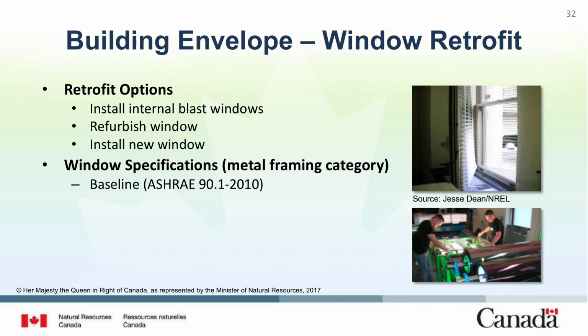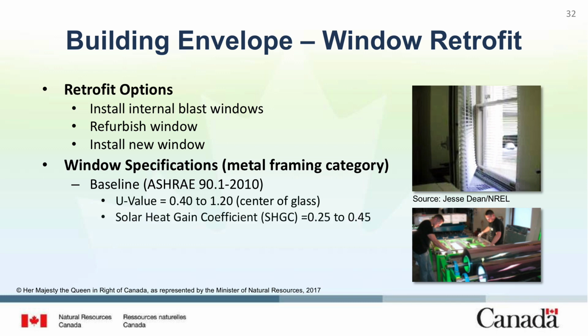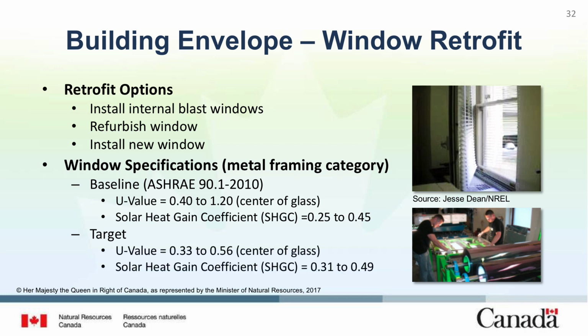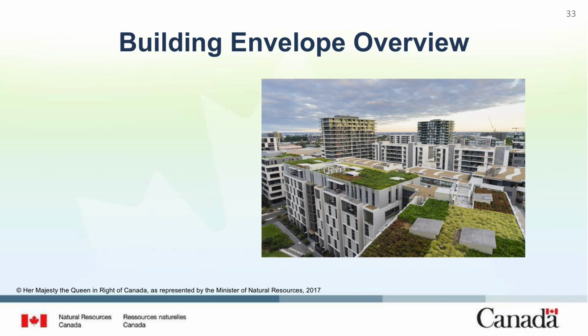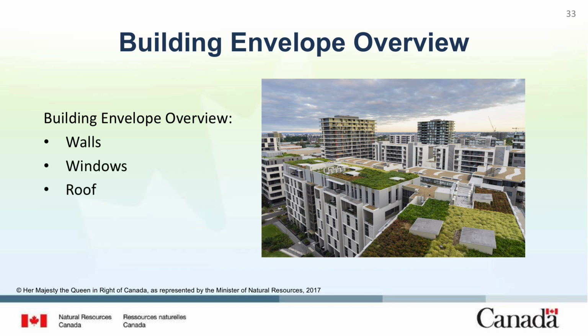If you choose to install a new window, you'd want to set aggressive performance targets. If you install new windows, there are options such as going from double to triple glaze, low E-coatings, and insulated frames. So to recap, for the building envelope, it's important to address the walls, the windows, and the roof, and as you're doing those, you should address air sealing within the facility. As you're addressing those window retrofits, make sure that you're putting in the appropriate windows to make use of daylighting, and also make sure that they're sealed appropriately so that you can implement other types of HVAC projects that we'll talk about here in a minute.